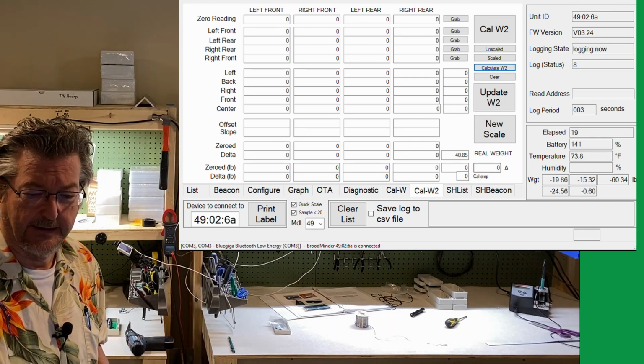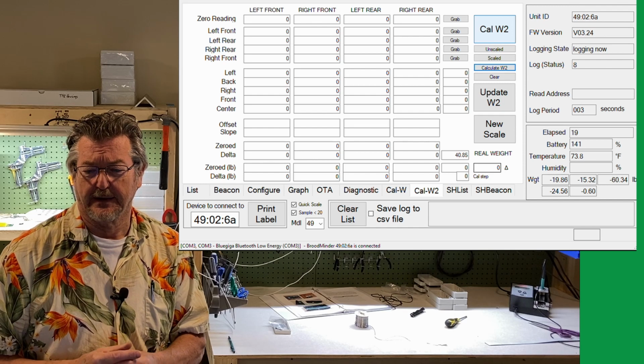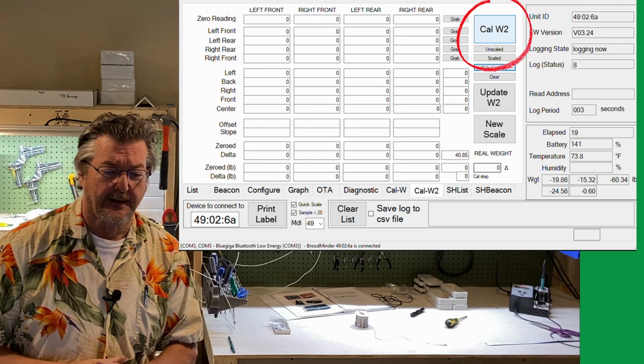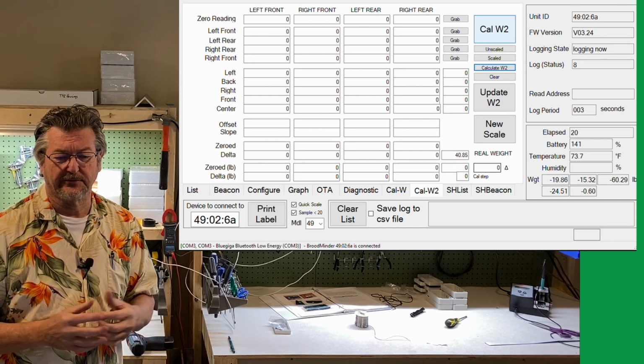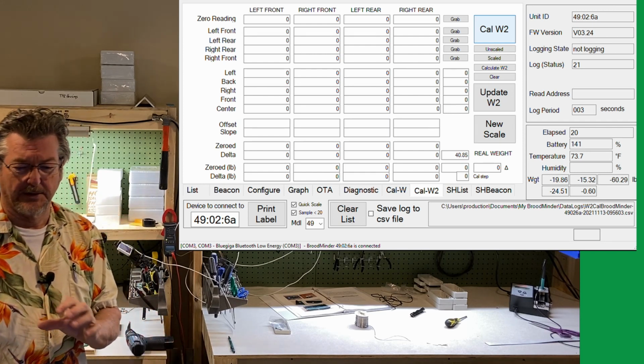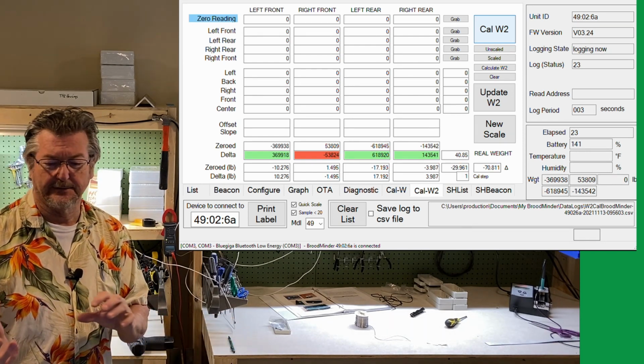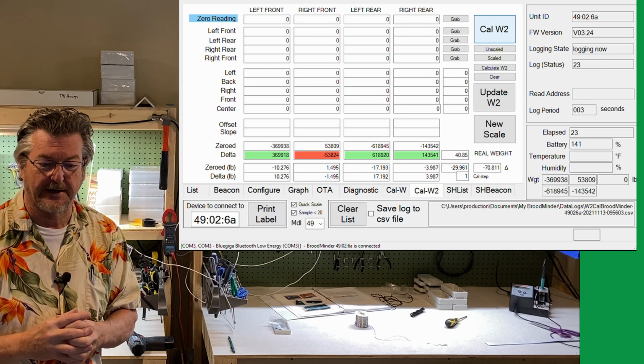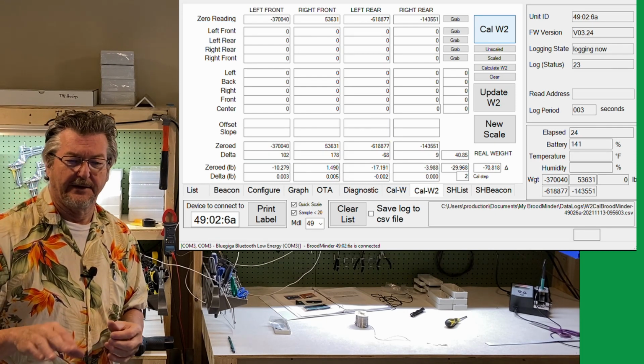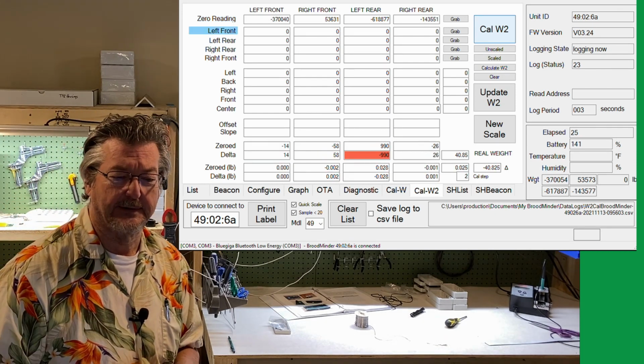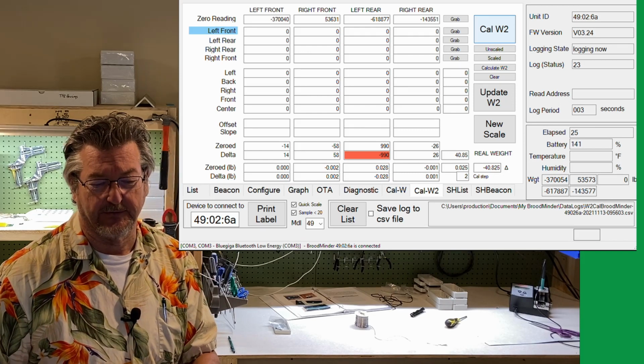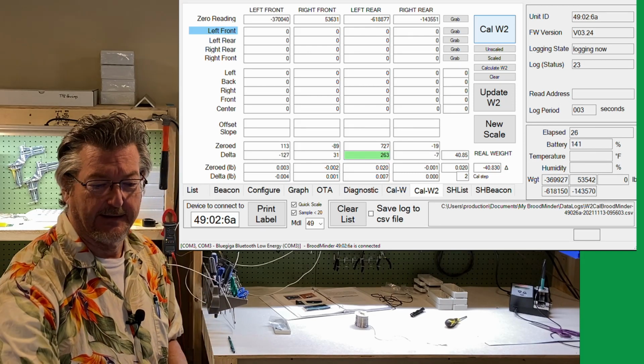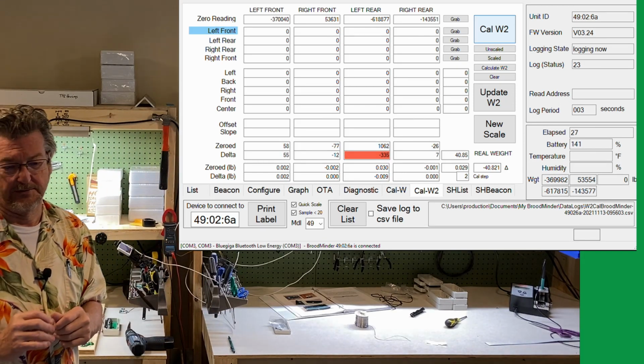Okay, so now we're going to hit Cal W2 up here at the top, and it's going to do a zero reading. It's changing its mode so that instead of reading pounds, it's reading the binary values out of the sensors. You can see in the top row it's read them now - it waits for everything to stabilize, and now it knows what zero is.